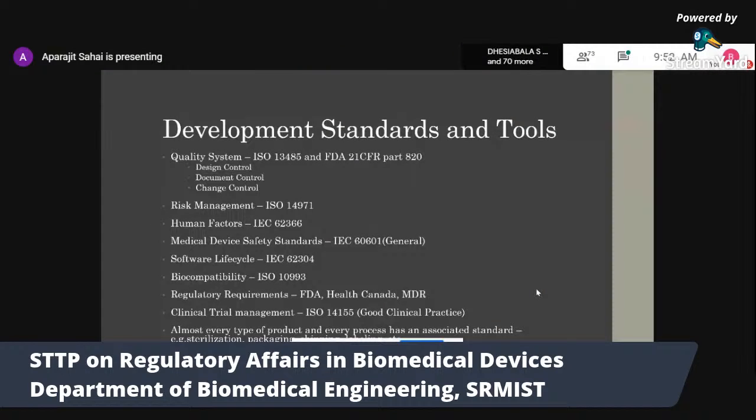Of course, there is a very important tool that is provided by regulators. Essentially, it's one regulator that's really good about it: the US FDA's guidance documents. I would recommend that everyone go and read the design control guidance by the FDA, because essentially every other regulator in the world, and even Europe, all follow design controls in one form or another.